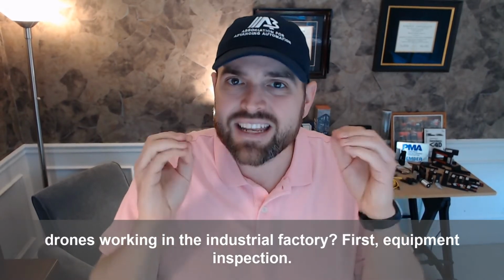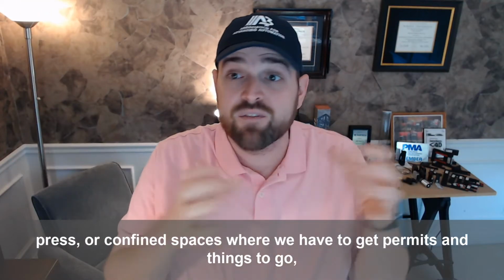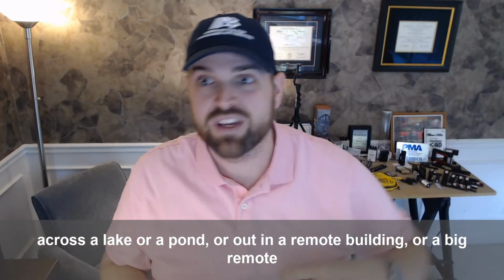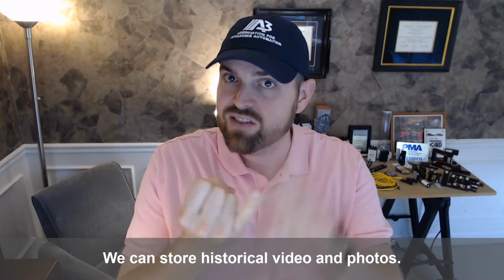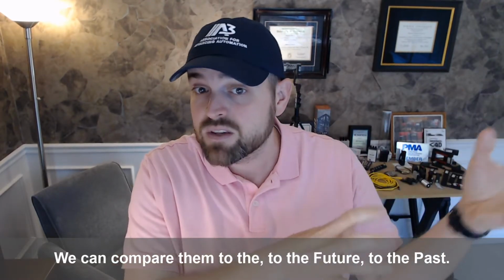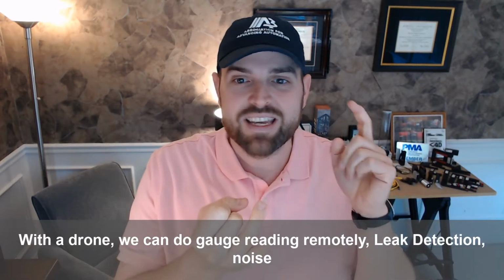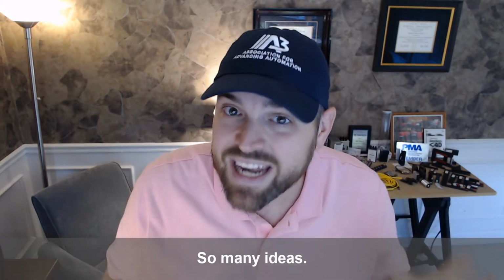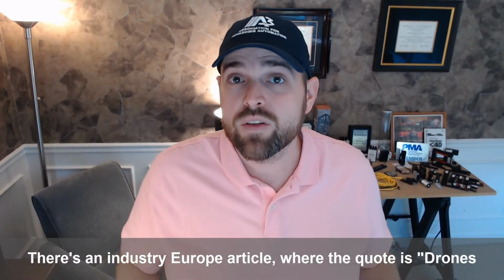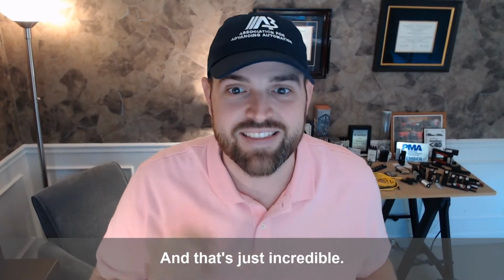First, equipment inspection, going places we can't reach easily, on top of equipment like the top of a stamping press, or confined spaces where we have to get permits, or across a lake or a pond, or out in a remote building, or a big remote facility with remote installations. What's cool about equipment inspection is we can store historical video and photos and compare them to the past. With a drone, we can do gauge reading remotely, leak detection, noise anomaly detection, thermal inspection, gas detection, so many ideas. There's an Industry Europe article where the quote is, drones cut Ford plant inspections from 12 hours to 12 minutes. And that's just incredible.